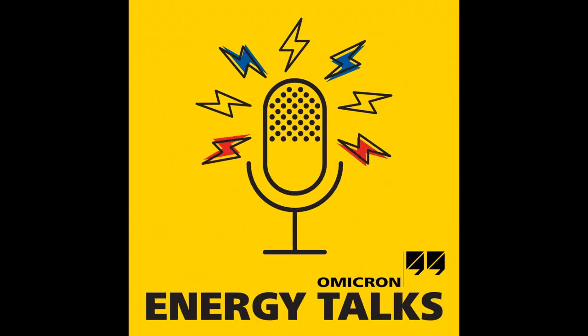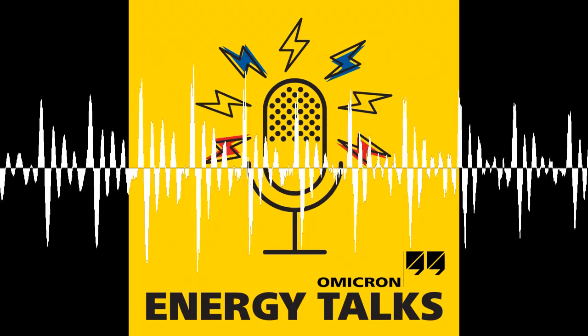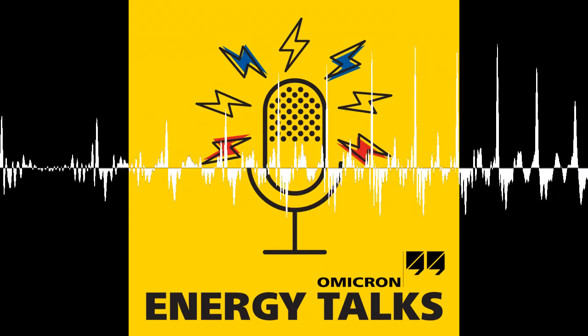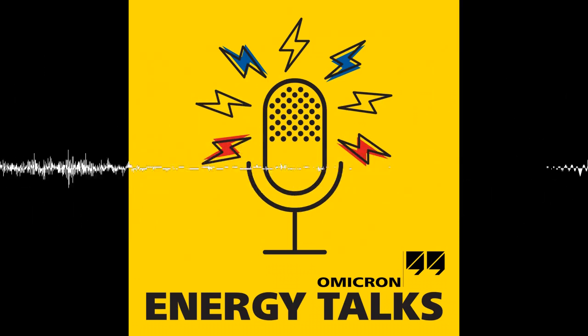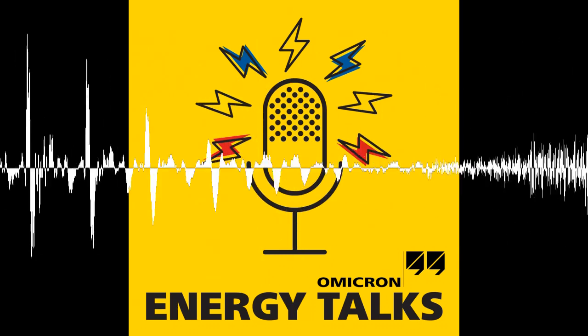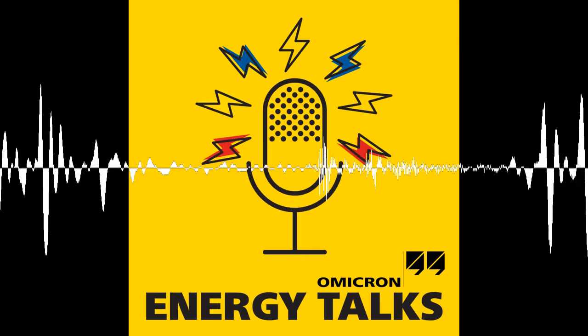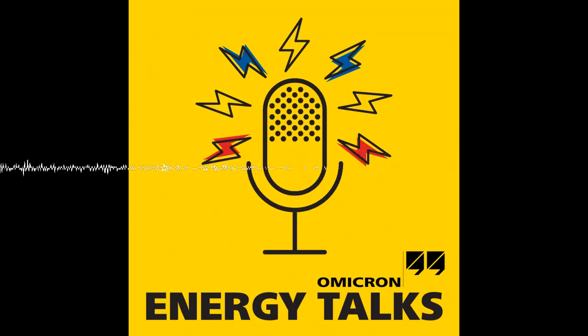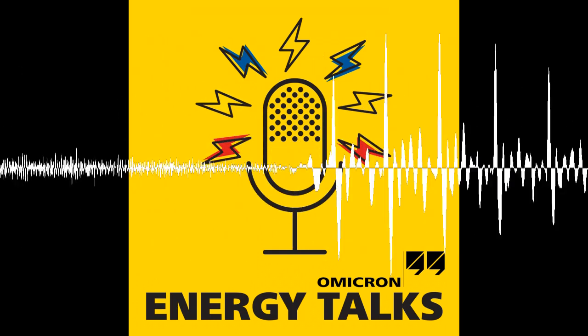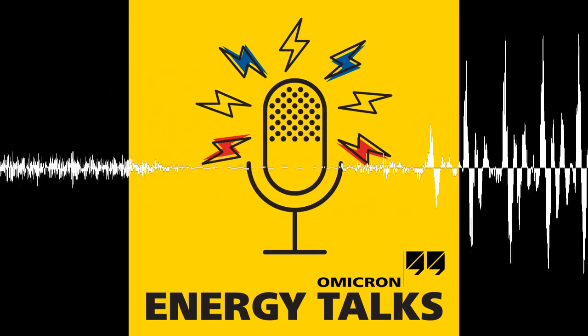Hello, everyone. In this episode of Energy Talks, we are going to discuss the analysis of on-load tap changers on power transformers. On-load tap changers, also known as OLTCs, are devices fitted onto power transformers that regulate the output voltage to required levels. With the help of the OLTC, the transformer turns ratio can be adjusted under load to deal with voltage fluctuations and maintain a stable voltage level in the electrical grid.